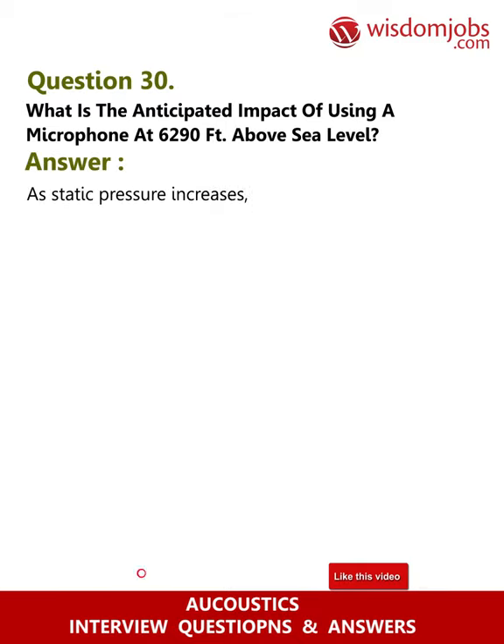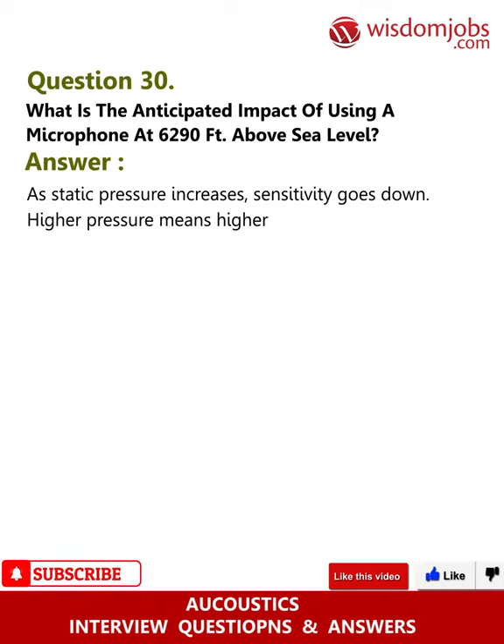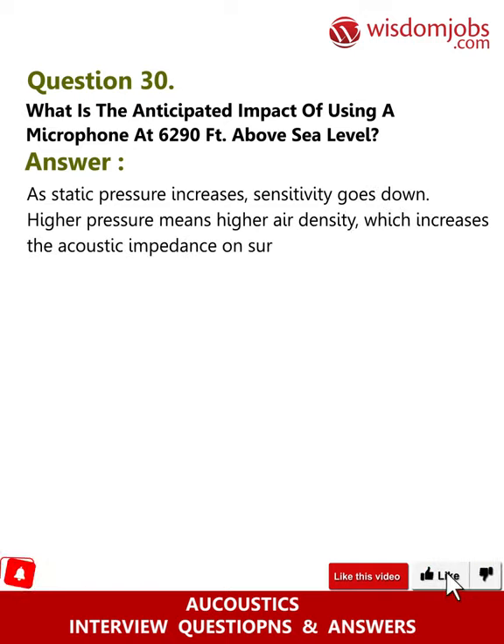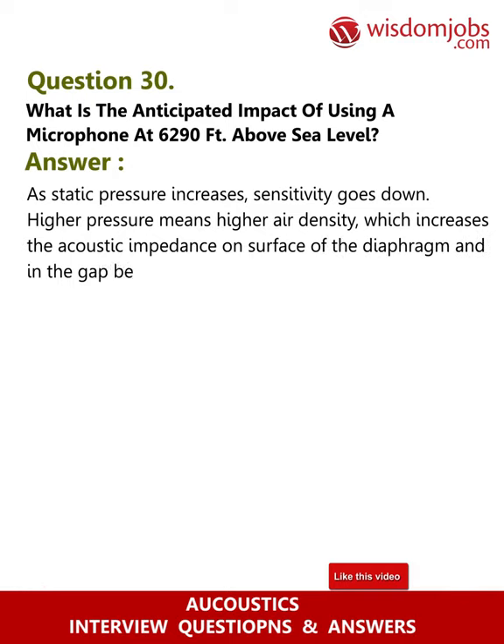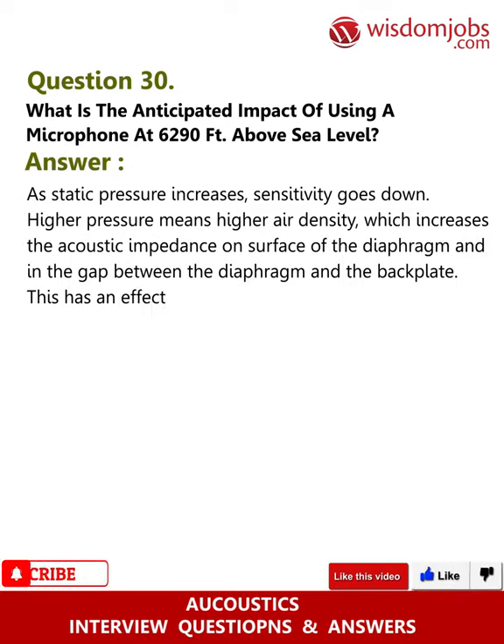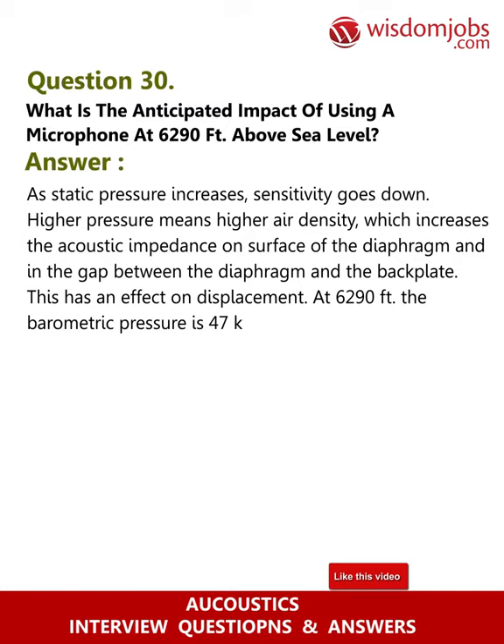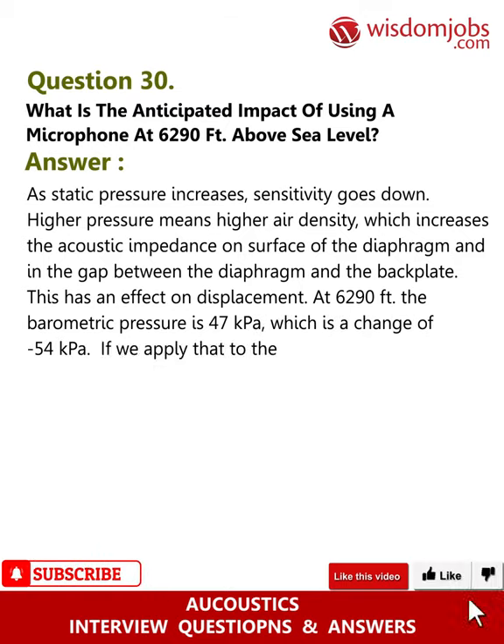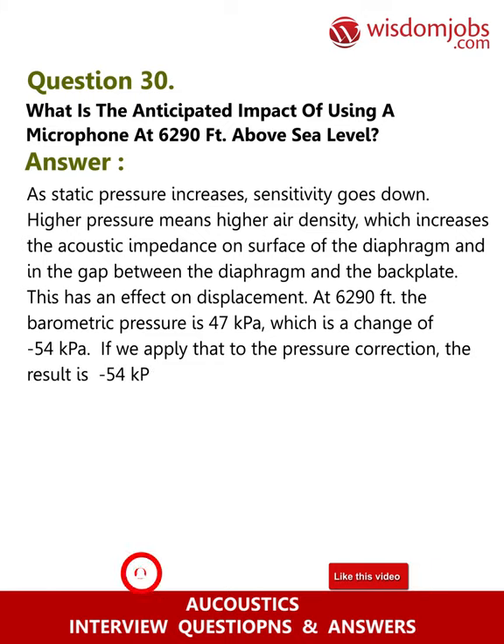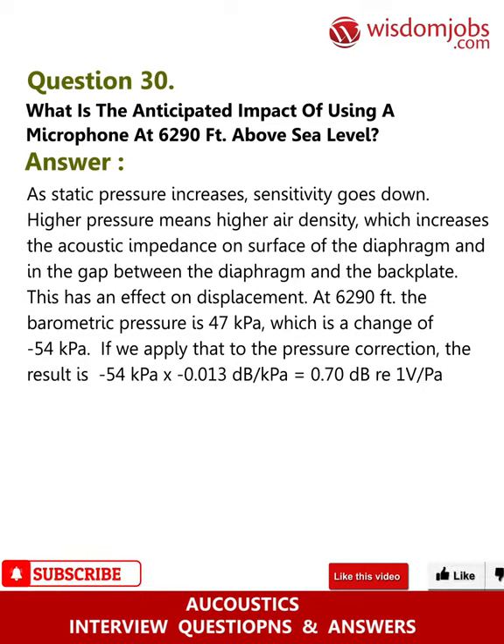Question 30: What is the anticipated impact of using a microphone at 6,290 feet above sea level? Answer: As static pressure increases, sensitivity goes down. Higher pressure means higher air density, which increases the acoustic impedance on the surface of the diaphragm and in the gap between the diaphragm and the back plate. At 6,290 feet, the barometric pressure is 47 kilopascals, which is a change of minus 54 kilopascals. Applying the pressure correction: minus 54 kilopascals multiplied by minus 0.013 dB/kPa equals 0.70 dB re 1 V/Pa.